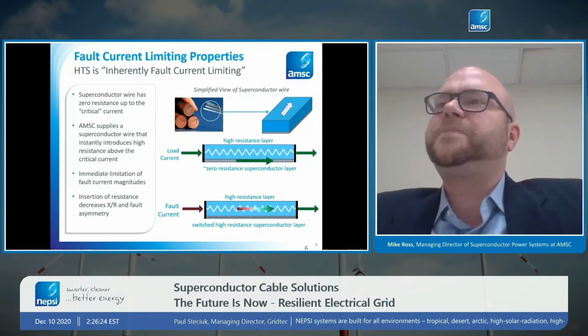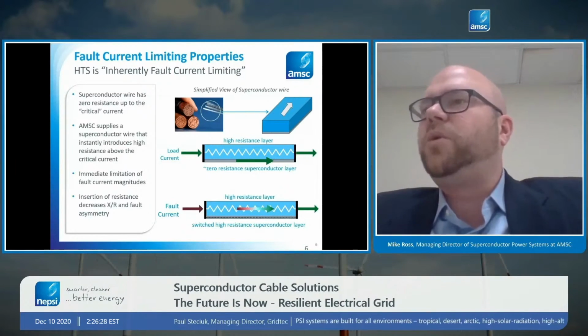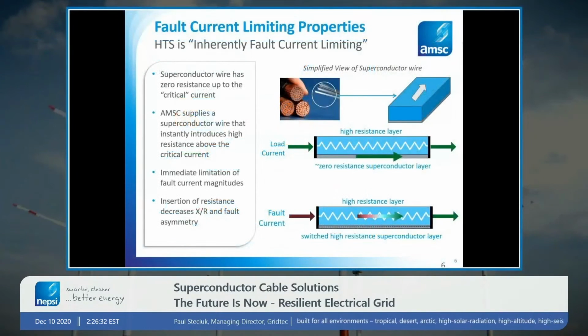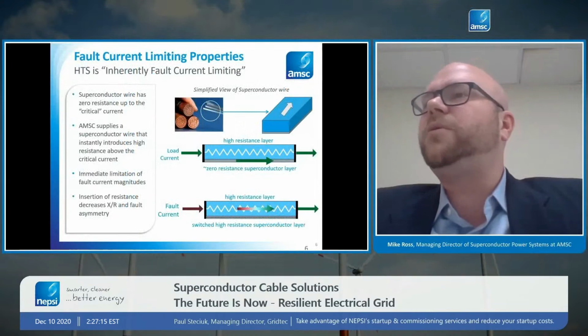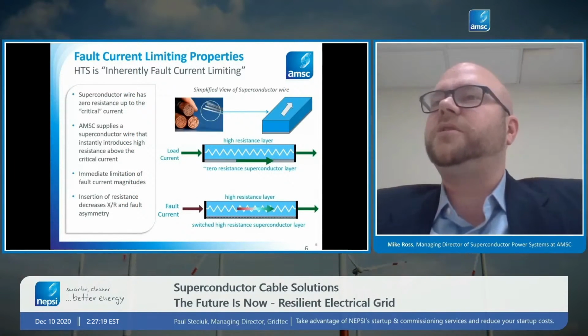So what we're seeing in this picture here is normal operation. Current runs through the wire, and all of the current runs through that very, very thin superconductor layer when we're superconducting in the normal conditions. So none of the current runs through the copper, brass, or stainless steel. But when there's a fault on the system and you try to drive high current through the wire, the superconductor layer stops being superconducting and pushes the current into those other metals. And that creates resistance, that creates impedance, and that limits the fault current. And we can control that to a certain degree by choosing the metal. Copper is relatively low resistance, stainless steel is relatively high resistance, and brass is somewhere in the middle. And then there are thicknesses and widths that we can adjust to further fine-tune the impedance. That's the way that we create the fault current limiting aspects of the material.